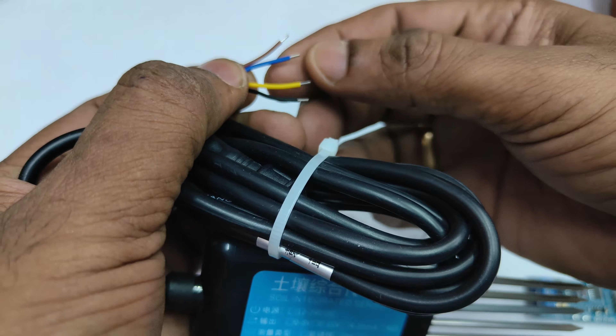The power required is 12 volt, 1 to 2 ampere, and the data signal is RS485. It has got 4 wires: the brown and black wires for power source, and the blue and yellow wire for RS485. Blue is B and yellow is A of RS485.